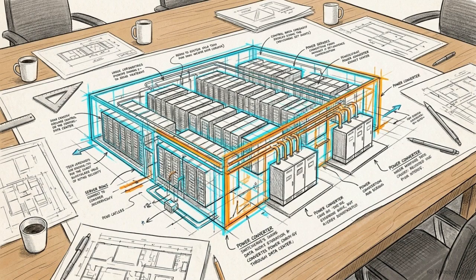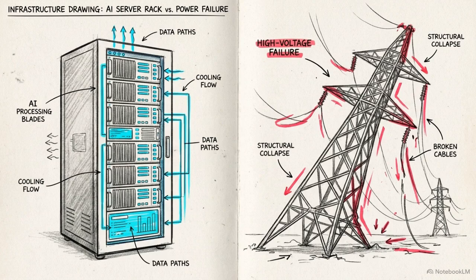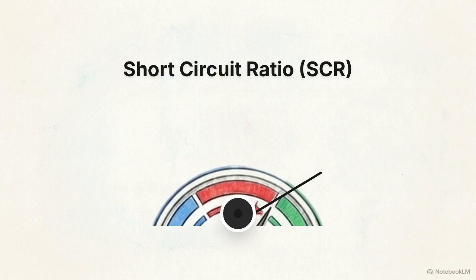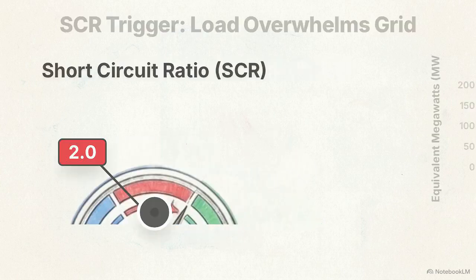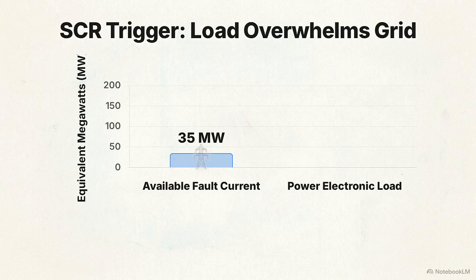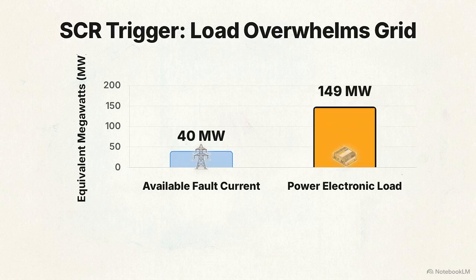While the need for an EMT study is clear, the actual engineering challenge is mathematically constructing a viable model of a hyperscale facility without causing the simulation software to crash. Integrating converter-dominated AI data centers using traditional average models prevents planners from identifying the high-speed triggers that lead to localized grid collapse. The requirement for an EMT study typically triggers when the short-circuit ratio falls below 2. This indicates a weak grid condition, where the available fault current is low relative to the massive power electronic load.